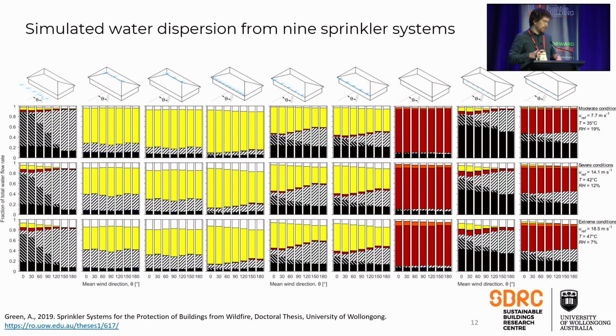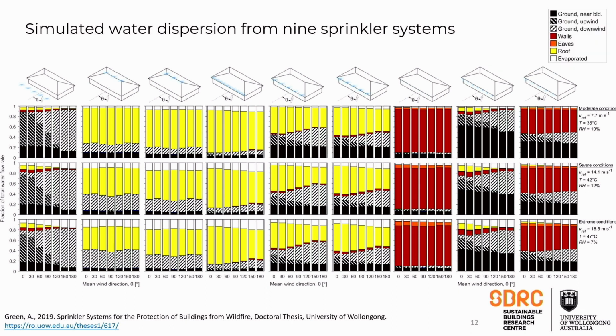This slide shows those types of results for all 9 sprinkler systems and the 3 different severities of conditions. There's a lot of information there we don't need to digest right now, but basically it shows that most systems aren't too sensitive to wind direction. The systems that spray water directly at the walls from under the eaves, the most right-hand column of data, and the third most right-hand, achieve a lot of water delivery to the walls, which is what they're designed to do, without being too severely impacted by wind. But if you look at the sprinklers on the roof, for example, when conditions become more severe, there can be 40% of the water that doesn't end up on the roof, or more, 50%.